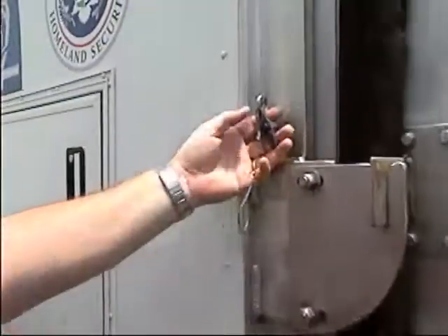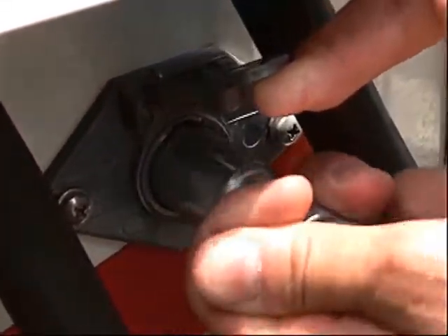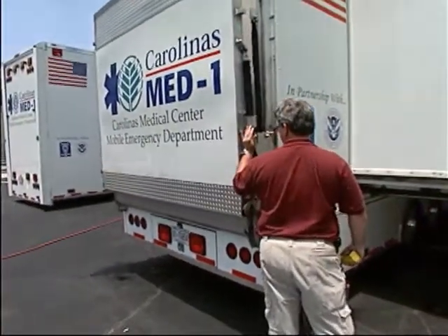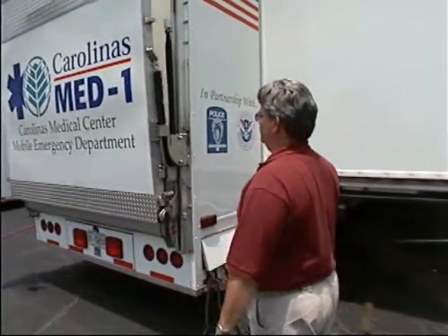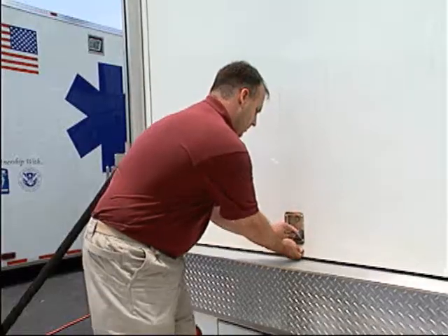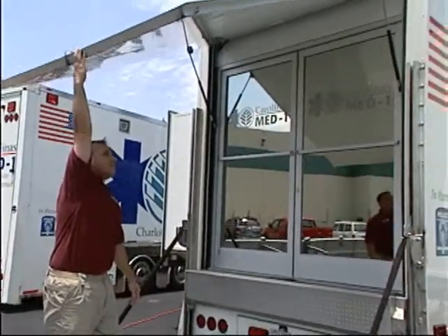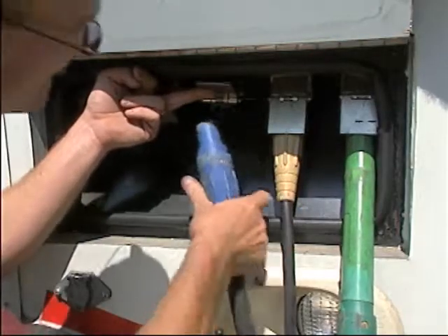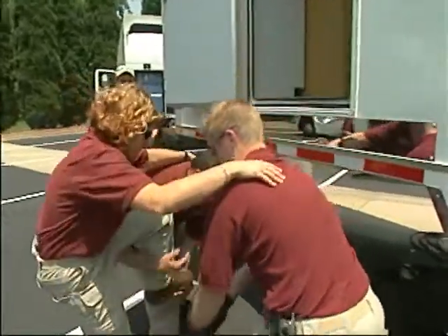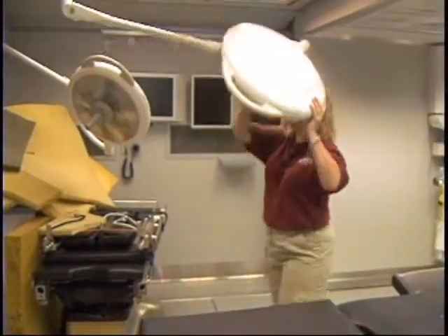The rear door of the hospital does not require external power, so the lift is made ready for use and the door is opened while the external power connections are made. Connections are color-coded and have distinct male-to-female connections to avoid mistakes during this process. One member of Team 4 will be hoisted into the closed operating room via a side access to unstow and guide the surgical lights. This will avoid damage from deployment of the OR slide-out.